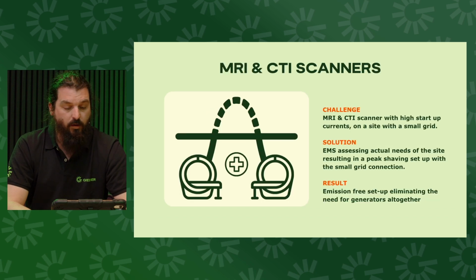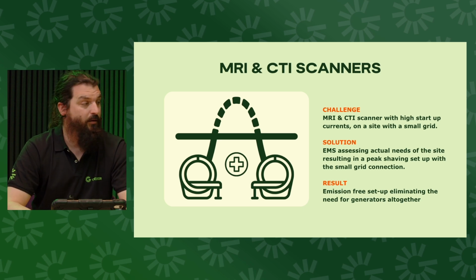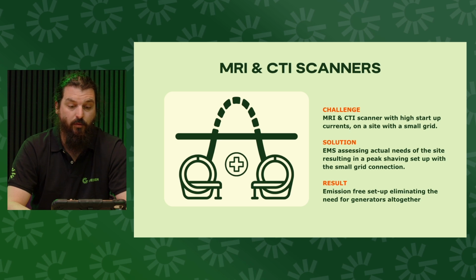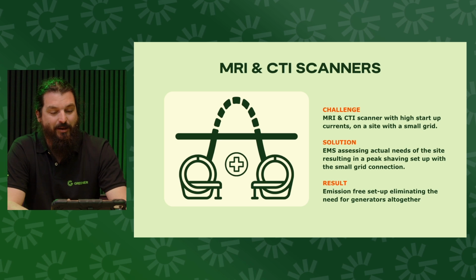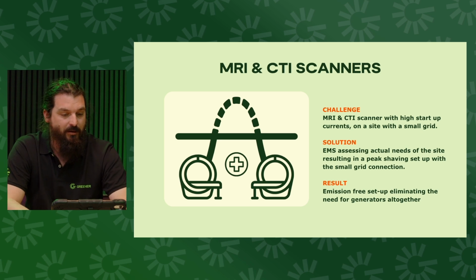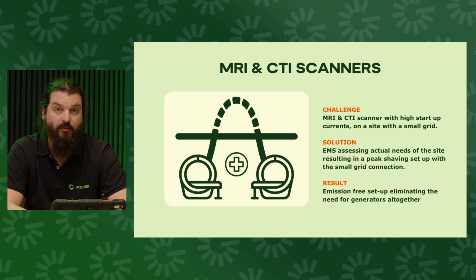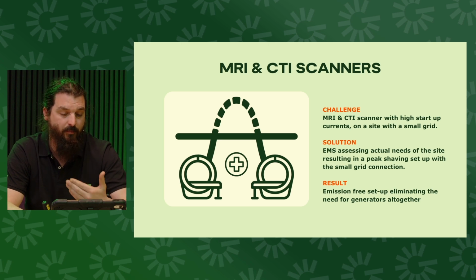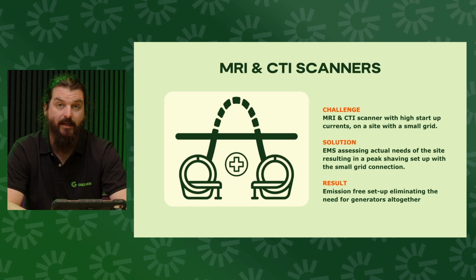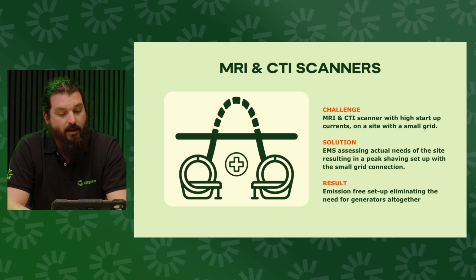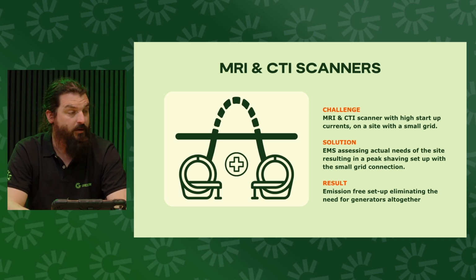So one of the jobs we did last year involved MRI CT scanners. For those who have been with us more than once, you've seen this one before. We had an interesting job where there were a couple of CT scanners which have high inrush currents due to the energy exciting the magnets upon start, and that drops away again very quickly once they are energized.